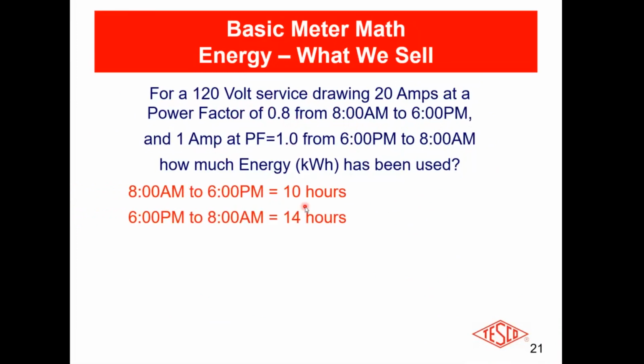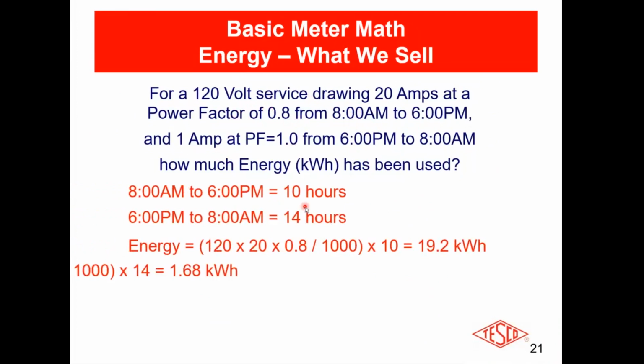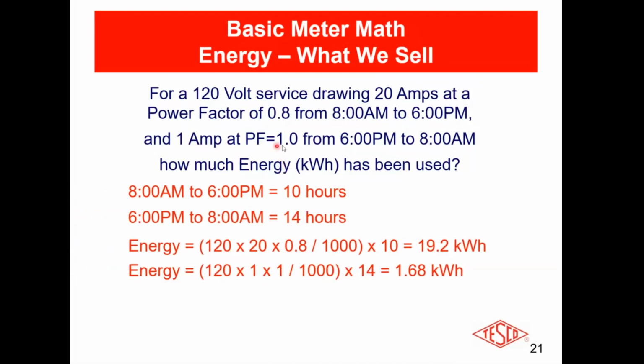I got 10 hours in the morning, 14 hours that I'm shut down, and I'm using 19.2 in the morning and 1.68 through the evening hours. So even though I've got a nice power factor, I'm not actually drawing that much energy because it's the evening, my plant's closed. And total for the day, I drew 20.88 kilowatt hours, or I paid for 20.88 kilowatt hours. You actually delivered more because my power factor during the day is kind of miserable.